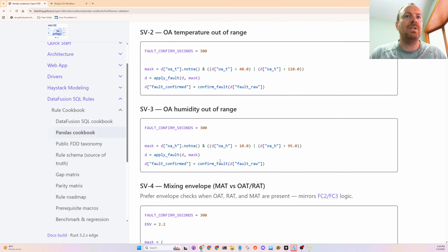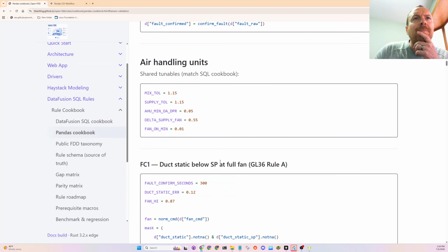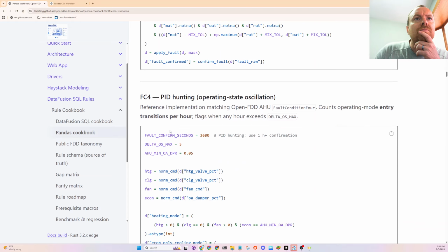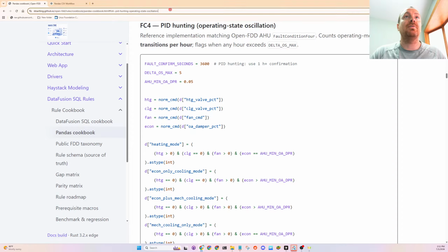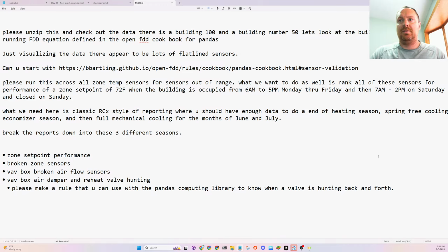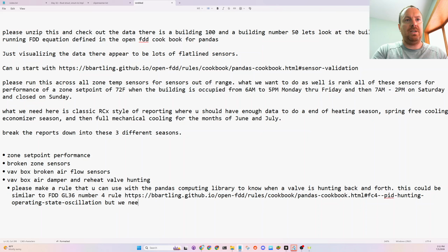Let me go back here. This should be kind of similar to here, this PID hunting fault condition 4 by Guideline 36. This could be similar to FDD Guideline 36, number 4, outputs and reheat valve commands.